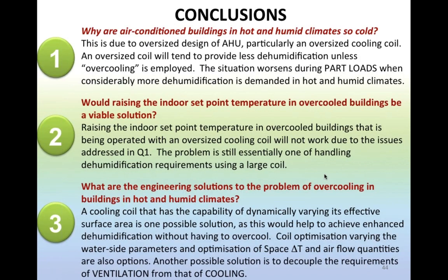And so an important outcome from here is that we need to look at the optimized coil configuration and its performance to ensure that we address the indoor air quality, the thermal comfort, and the energy aspects of it. So I would like to conclude by going back to those same three questions. Why are air-conditioned buildings in hot and humid climates so cold? What I mentioned earlier and discussed with you is that it is due to the oversized design of the air handling unit, particularly the cooling coil, and an oversized coil will tend to have less dehumidification unless we employ overcooling. And this situation worsens when we are looking at part loads.